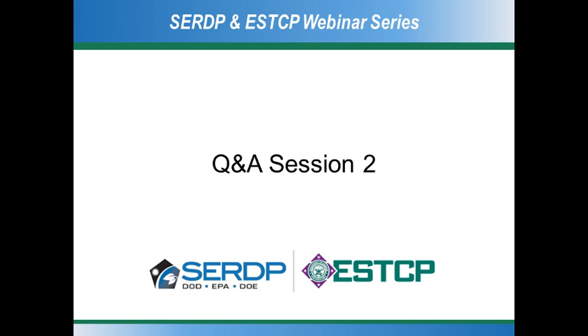The first thing is that BTES systems are always active. So we're not just sticking these passive boreholes down in the ground, hoping the energy will match in and out and the system will stay uniform in temperature over time. That's just not reality. There is some argument within the community of geothermal heat pump nerds like myself, you know, how much the ground heats up and all of that, but the physics are pretty straightforward. If you pump more heat in the ground than you take out, over the long term, the ground's going to warm up. So the first good thing about a BTES system, in my opinion, is they're always active. You are actively managing the ground.